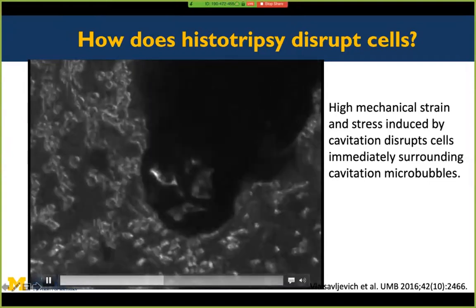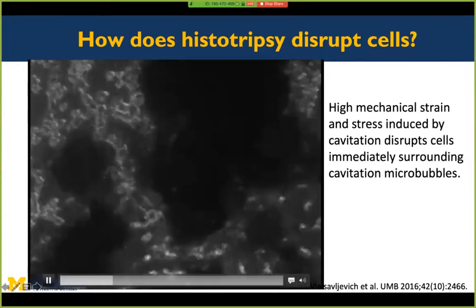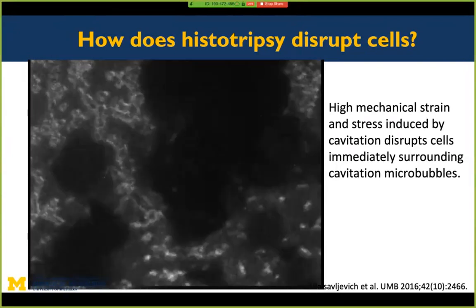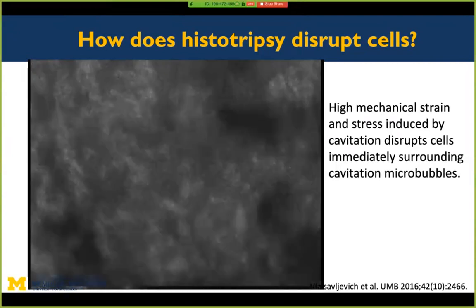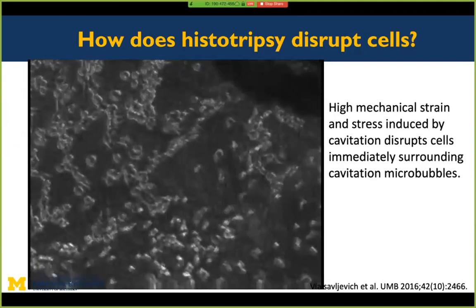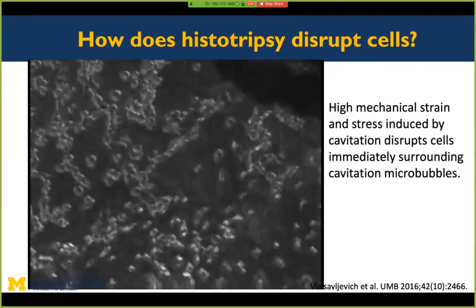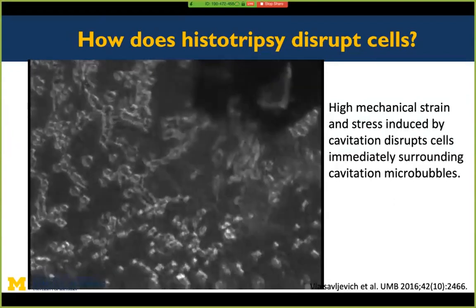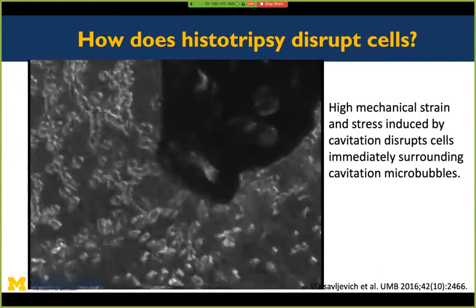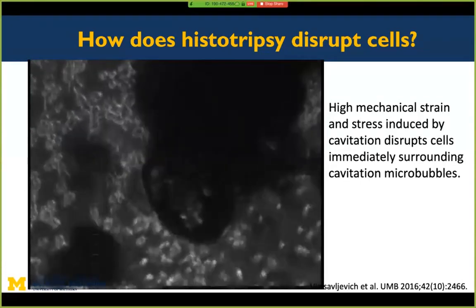Microsecond-length pulses allow reliable cavitation generation. The bubble expansion-collapse process takes several hundred microseconds, then residual bubbles dissolve. If the pulse length is extended to milliseconds, bubble activity becomes chaotic and less controllable. The low duty cycle in histotripsy serves two purposes: reducing heating, and providing sufficient time between pulses for residual bubble fragments to dissolve so they don't impact cavitation generated by the next pulse.